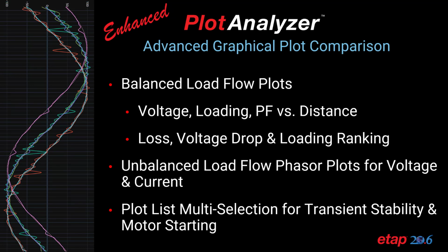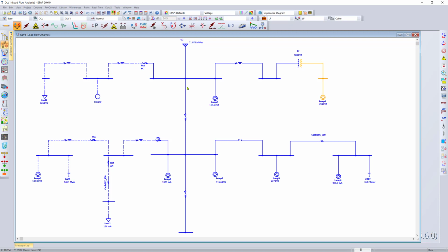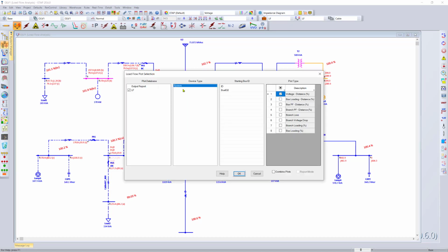ETAP Plot Analyzer is an advanced graphical plot comparison tool that was introduced in ETAP 20 that is available in all ETAP analysis modules. We have expanded the capability of Plot Analyzer, allowing it to perform even more unique computations, especially for balanced load flow as well as unbalanced load flow. So let's go ahead and take a look at these two examples in ETAP 20.6. You can simply load up your favorite example file, run the load flow calculation, visualize the results, and now you have access to the plot analyzer directly in the load flow program. The program automatically selects the swing bus, and then you can choose between different plot types for visualizing the results in the plot analyzer.